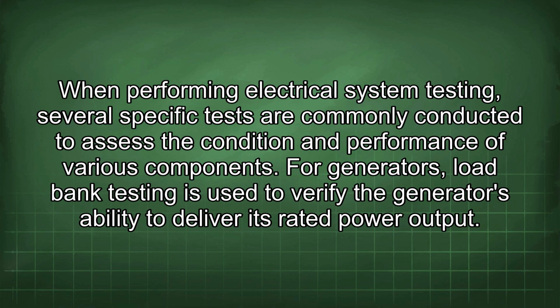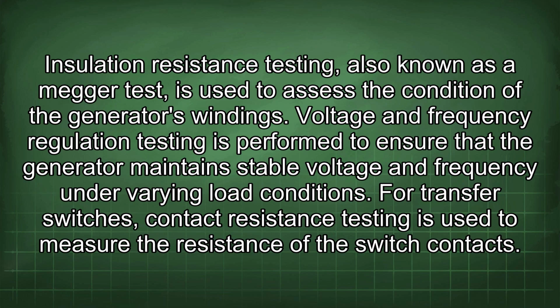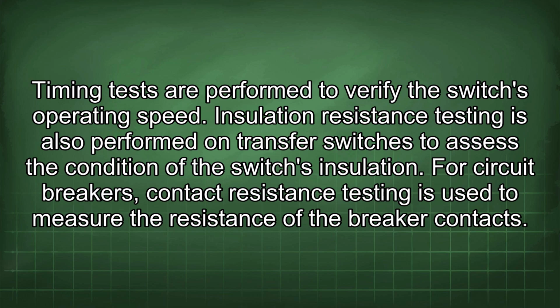When performing electrical system testing, several specific tests are commonly conducted to assess the condition and performance of various components. For generators, load bank testing is used to verify the generator's ability to deliver its rated power output. Insulation resistance testing, also known as a Megger test, is used to assess the condition of the generator's windings. Voltage and frequency regulation testing is performed to ensure that the generator maintains stable voltage and frequency under varying load conditions. For transfer switches, contact resistance testing is used to measure the resistance of the switch contacts. Timing tests are performed to verify the switch's operating speed. Insulation resistance testing is also performed on transfer switches to assess the condition of the switch's insulation.